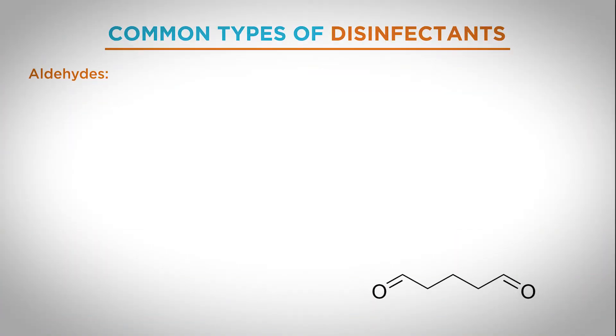Another important class of disinfectants are aldehydes, namely formaldehyde and glutaraldehyde. These are cross-linking agents, meaning they denature proteins and soils and fixate them to surfaces. Aldehydes are also used as fixating agents in microscopy. This is relevant because if we don't perform the cleaning process properly, there will be soils on surfaces that get cross-linked by the aldehyde disinfectant, making them very difficult to remove in subsequent cleaning steps.